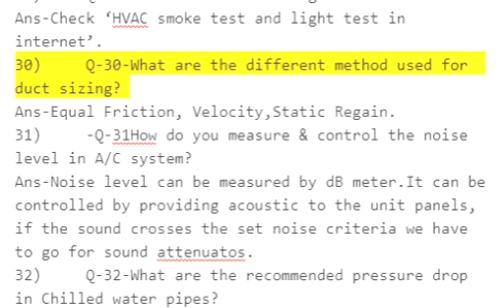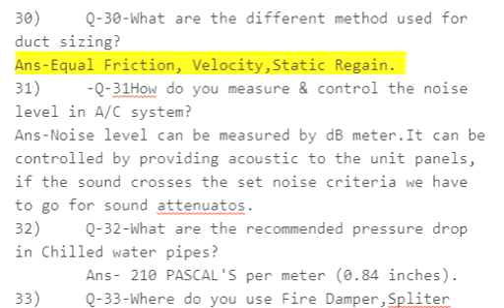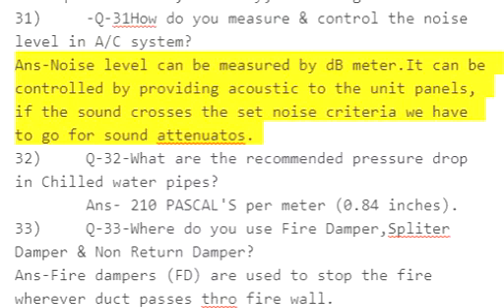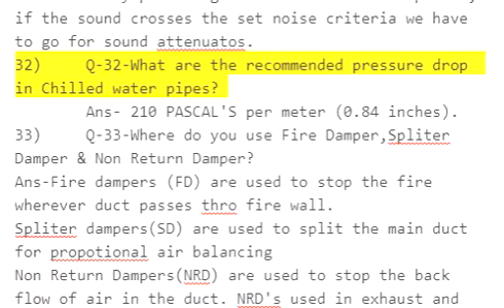Q30: What are the different methods used for duct sizing? Answer: Equal friction, velocity, static regain. Q31: How do you measure and control the noise level in an AC system? Answer: Noise level can be measured by a dB meter. It can be controlled by providing acoustic panels to the unit. If the sound crosses the set noise criteria, we have to go for sound attenuators.